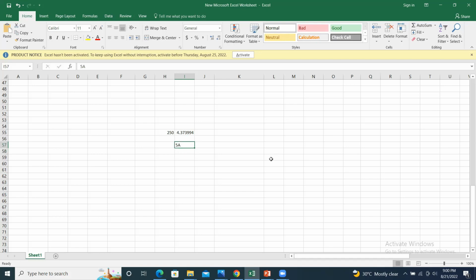Yesterday I already talked on this. My auxiliary transformer costs me 4 or 5 lakhs or maybe less than this. So for this, placing of the breaker and adding the protection, the whole thing is not viable, because my capital cost is X, but I am placing protection which is nearly 70% of X. It's not good. It should be less than 20%.